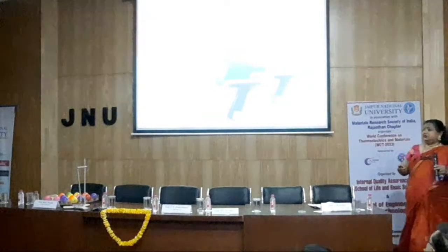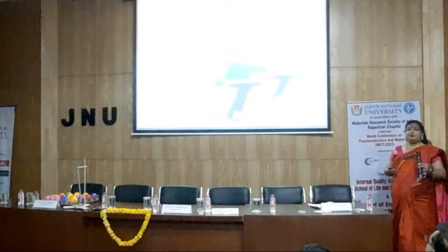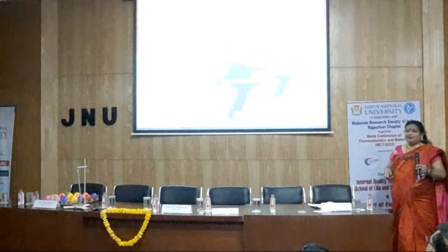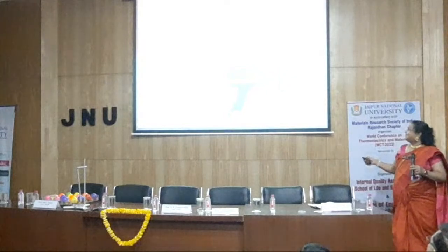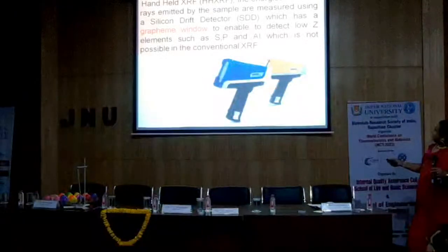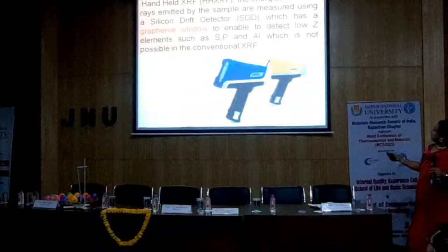I did that for almost 20-25 years, and then they said no, she is getting older, she needs a small detector, which is a silicon drift detector, and it has a graphene window to detect sulfur, phosphorus, aluminum, which is not possible in conventional ones. Next.